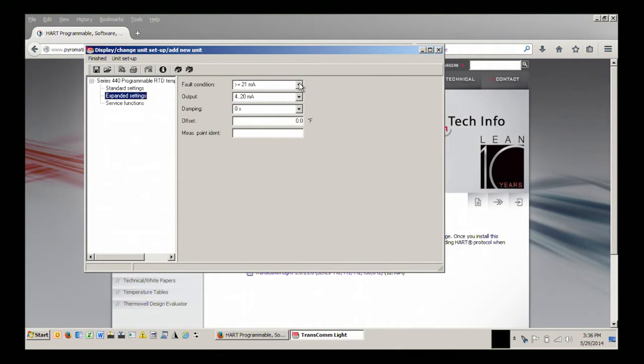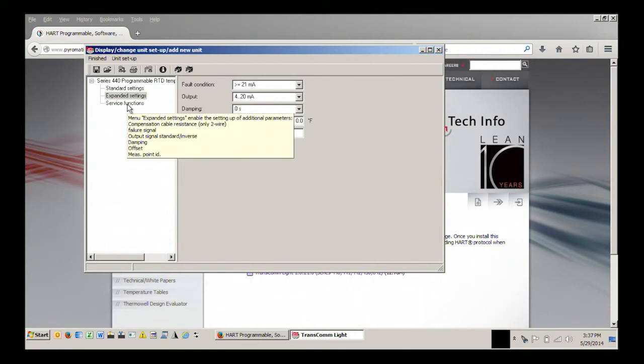Expanded settings, the fault condition is either to the upscale or to the downscale, less than 3.6 milliamps or greater than 21. Output can be 4 to 20 milliamps or 20 to 4. Damping can be set from 0 up to 8 seconds. Calibration offset can be applied if necessary.